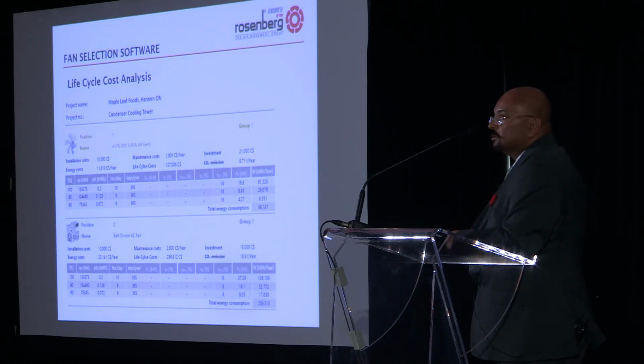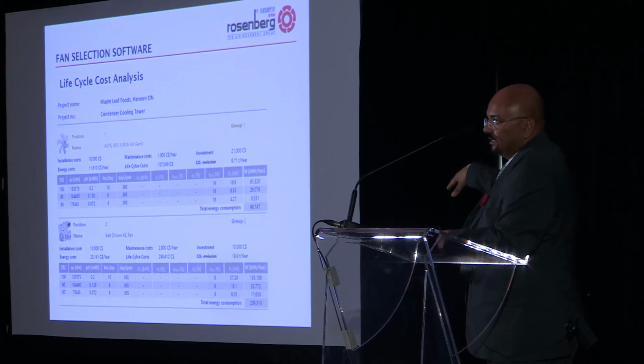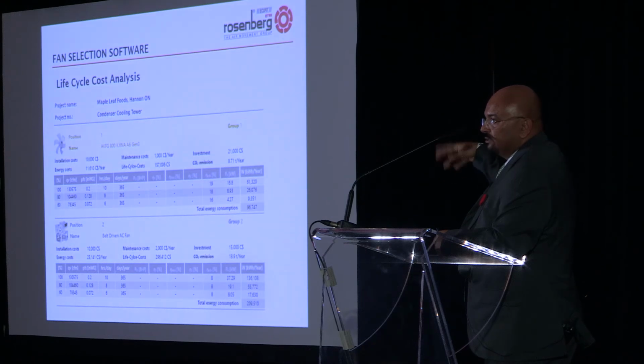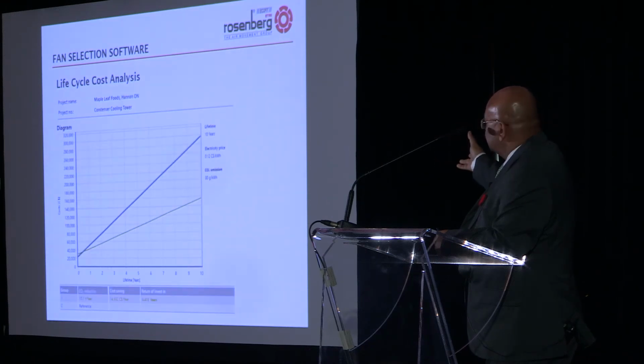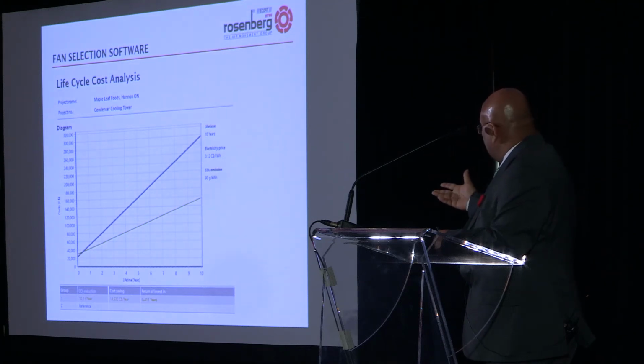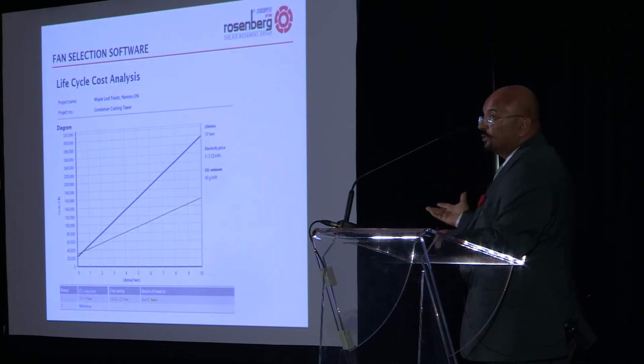This software can also get you a life cycle cost analysis. So you can actually input your data for the existing fan and the existing fan what you have at the site. So based on these two different data, it can actually tell you the ROI. So for example, in this, the ROI is less than half a year, 0.4, right? And the CO2 emissions is close to about 10.1 tons, which is a reduction in CO2 emissions. At the same time, the cost savings is close to about $14,000 a year. That's the energy savings, just the energy savings.